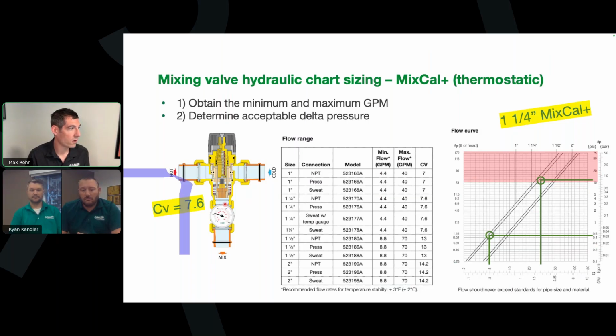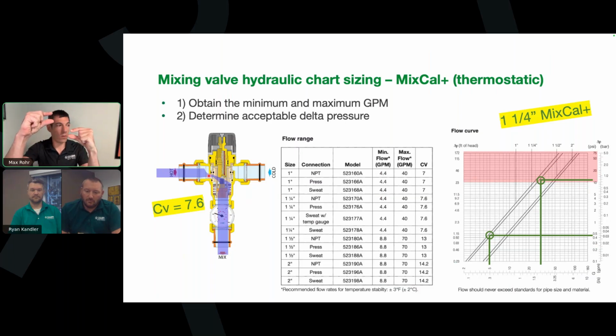This is the flow, the path of water going through a thermostatic mixing valve. So you have a pinch point right here because you have the hot and the cold, on the left is the hot, the right is the cold. And then you have that tan shuttle in the middle that's moving up and down to give you a different ratio of hot and cold. So there's kind of a pinch point here. This is a small passageway for water to flow through a valve. Works great. This is some of the most stable technology in plumbing. This is very, very simple. We just have a wax element that's expanding and contracting to give you a different ratio there. But it is a little bit of a pinch point for a pressure drop.